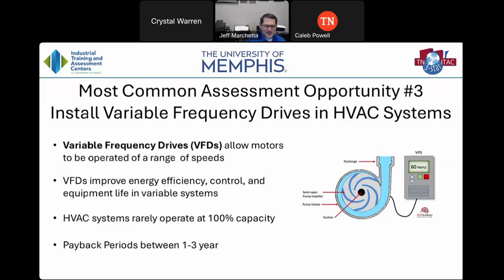So for HVAC systems, VFDs are great because they adjust your pressures and flow rates and your fan speeds based on the outside conditions and the inside conditions that you're trying to achieve for the environment. They're great on energy efficiency because you're no longer having to stop and start equipment. You're basically adjusting or modulating those variables through speed control on the VFD drive. HVAC systems rarely operate at 100% capacity because they're sized for some of your hottest degree days or coolest degree days. So other than a very hot day in July or a very cold day, you know, a couple weeks ago here, your system is not operating at the capacity to handle those extremes. They're operating in the middle, and that's particularly true in the fall and springtime.